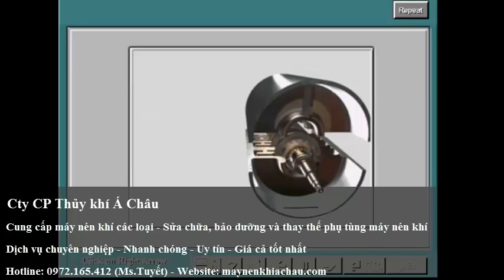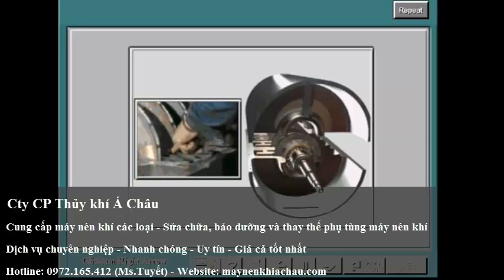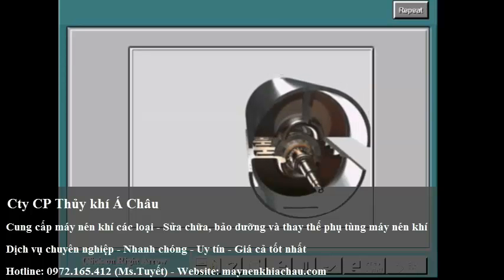Before closing the counter casing halves together, O-ring segments, coated with lubricating grease, are fitted into position on the middle split plane of the lower diaphragm to minimize leakage between compression stages. Great care must be taken to ensure a perfect fit between the two halves to avoid internal damage to the rotor and diaphragm.